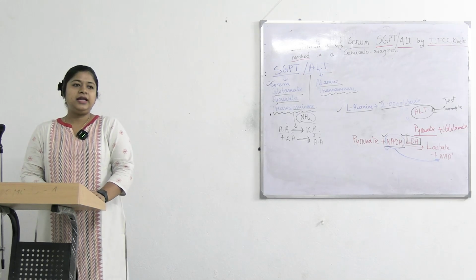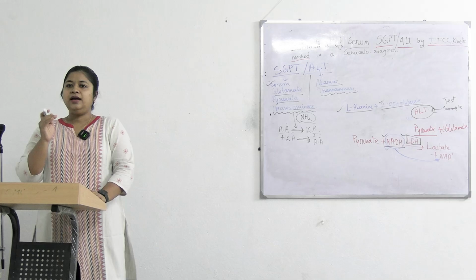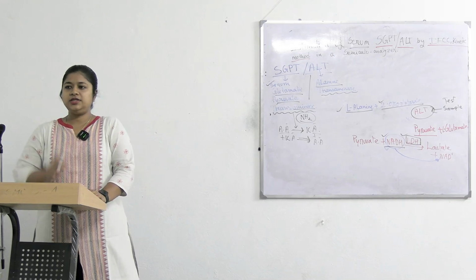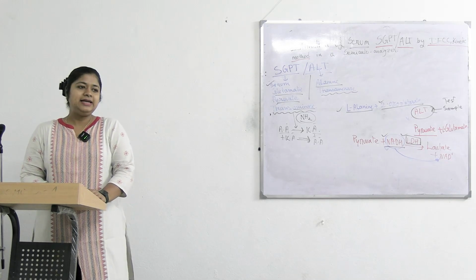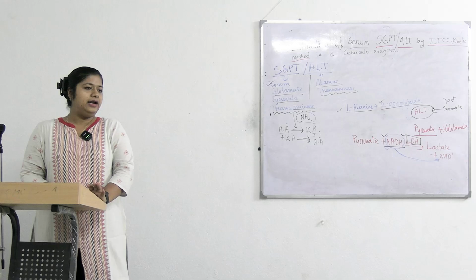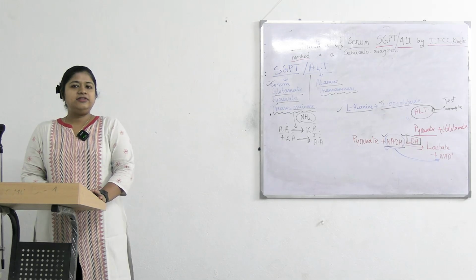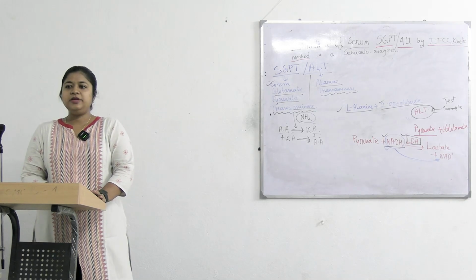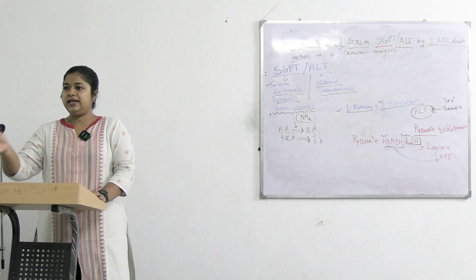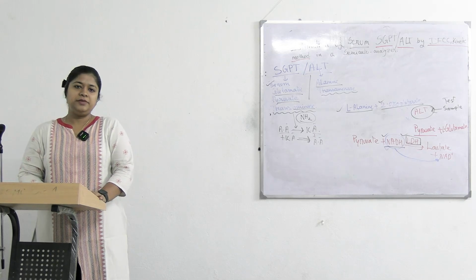But here the machine waits for 60 seconds for the first reading. So lag time is 60 seconds and kinetic interval is also 60 seconds. That means after each 60 seconds the machine will take a measurement.